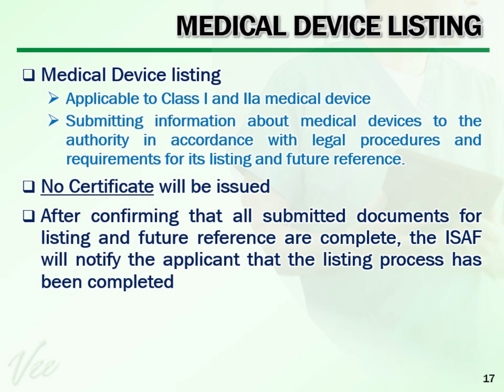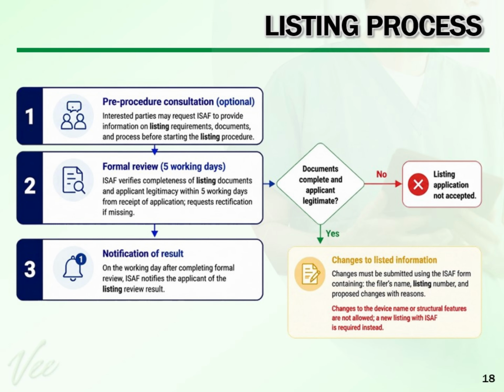For Class 1 and 2 a medical device, listing involves submitting information about the medical device to the authority in accordance with legal procedures and requirements, so the device can be recorded for listing and future reference. No certificate is issued under this process. Once ISAF confirms that all submitted documents are complete, it notifies the applicant that the listing process has been completed. Here is the listing process in Macau.